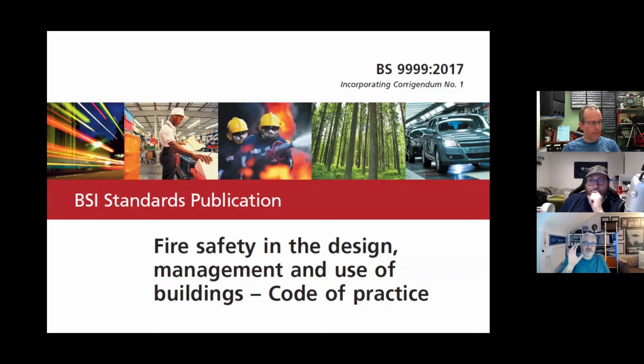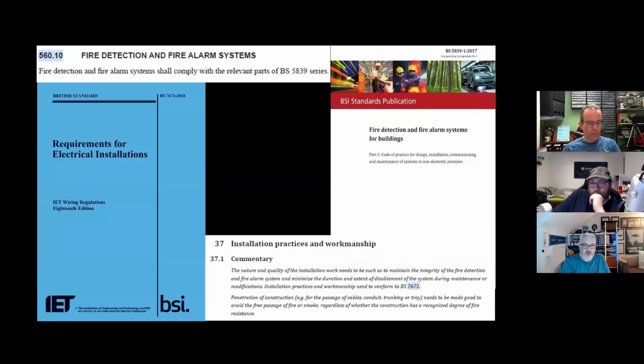BS 9999 is part of a suite of standards. In the hierarchy of fire safety management, you'll have the legislation, the Regulatory Reform (Fire Safety) Order, then the building regulations Part B. If you can't find or use Part B, you go down to BS 9999, fire safety and design management and use of buildings. You can then go to a quantitative assessment method, another British standard. I'm very pleased this is now coming into the regulations, and it's fairly evident why, probably post Grenfell.